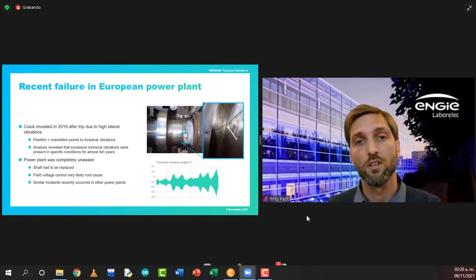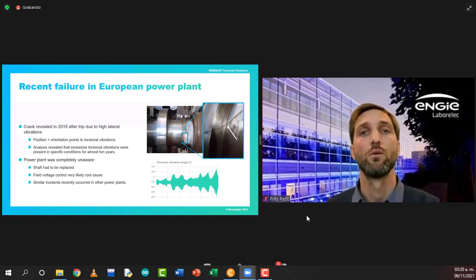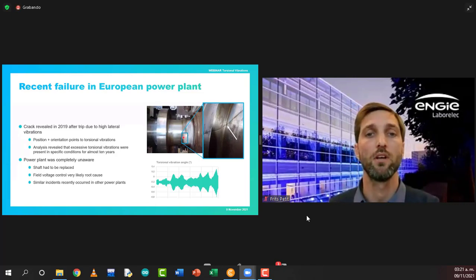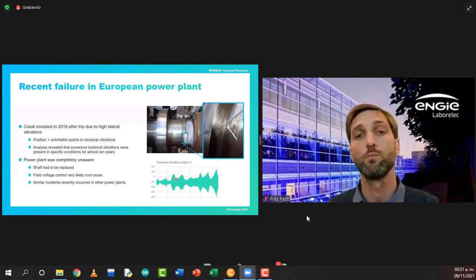So you can see the position, this was confirmed by a finite element model, but also the orientation at the 45-degree angle is a typical feature of torsional vibration, already suggests that torsional vibrations are present. And then later analysis actually showed that this phenomenon was already ongoing for more than 10 years. So intermittently, when certain conditions were present, the torsional vibrations were increasing. As you can see here below, for instance, in a temporary measurement campaign we performed, we identified these torsional vibration excursions. And so in certain conditions, this phenomenon was set in, accumulating fatigue damage, and over time creating, in the end, a crack initiation. The power plant was completely unaware.